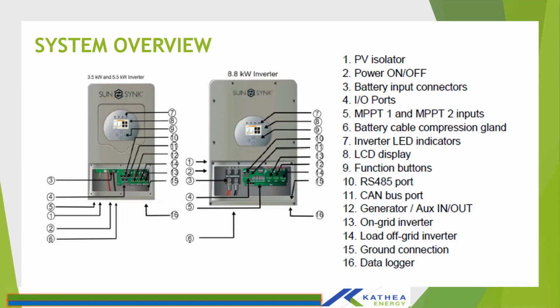Okay, the top part, when the inverter is working on off-grid mode, then your neutral will be live. So on wiring, that's how it's prescribed by SunSynk. And we have actually made a query with them, and they said that's how the inverter works. So when wiring, you should follow the labeling on the PCB port, because the upper part is for the internal circuit. That's why it's connected in that format.